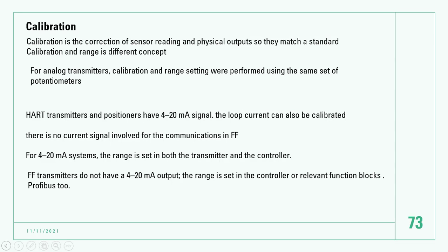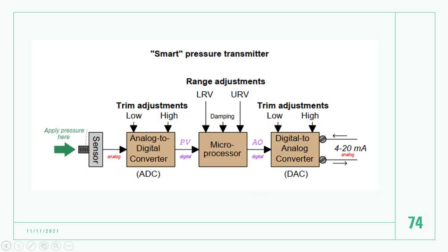It's the same thing as Profibus. This is a smart pressure transmitter, a HART communication transmitter. Okay, this one has trim adjustment and range adjustment. All these transmitters have 3 blocks: ADC, microprocessor, DAC. Okay, if you trim the sensor here, if you trim here is the output. Okay, then if you range, you do it here.